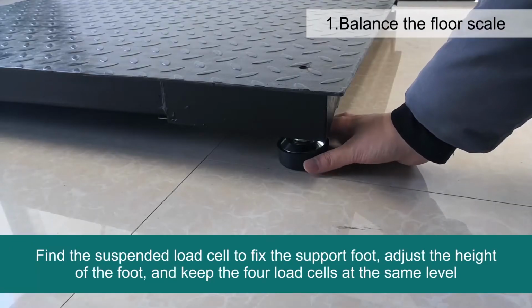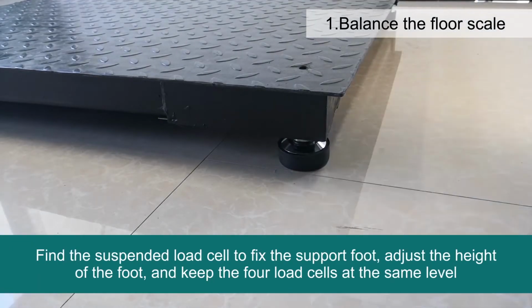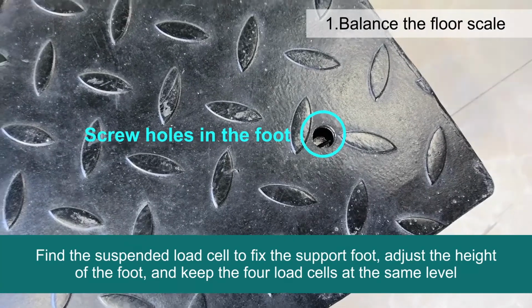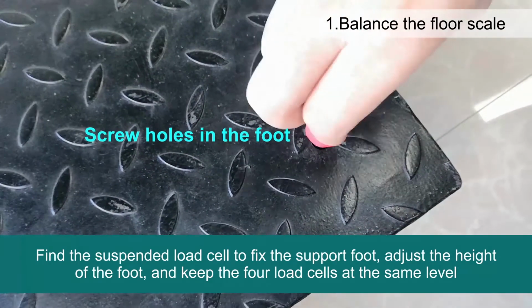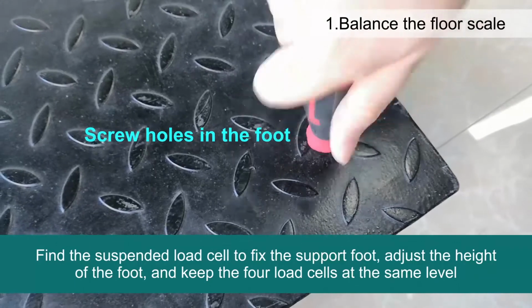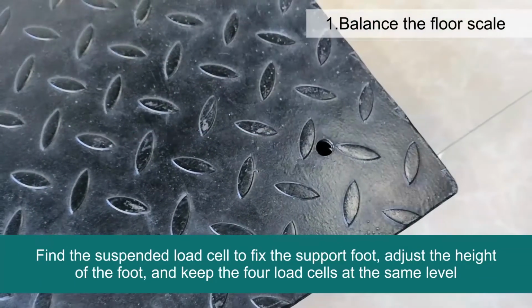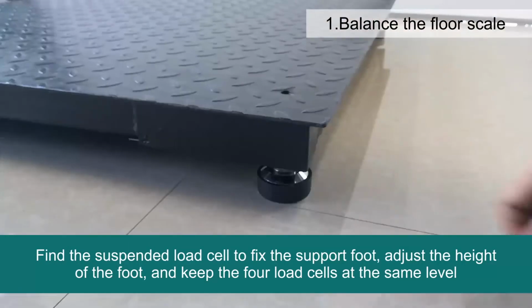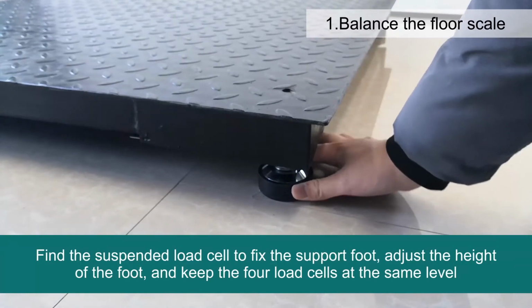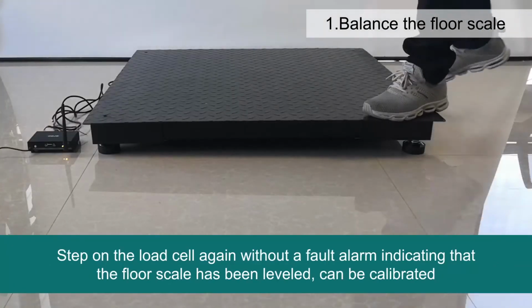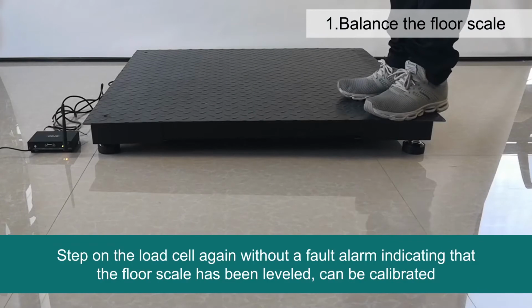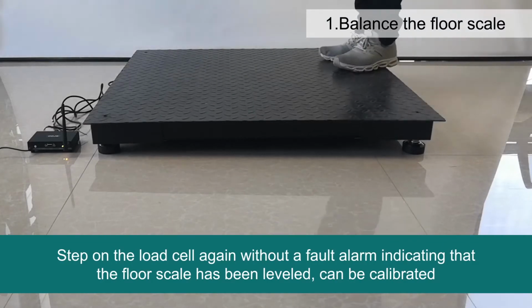Find the suspended load cell to fix the support foot. Adjust the height of the foot and keep the 4 load cells at the same level. Step on the load cell again. Without a fault alarm, the floor scale has been leveled and can be calibrated.